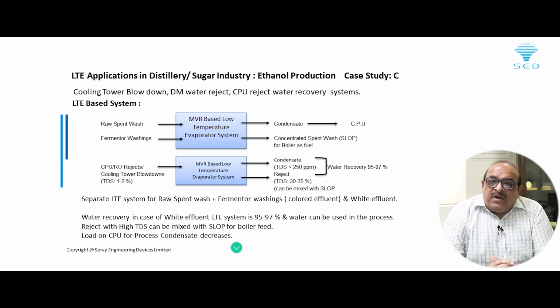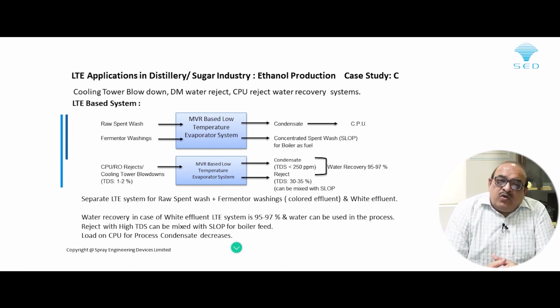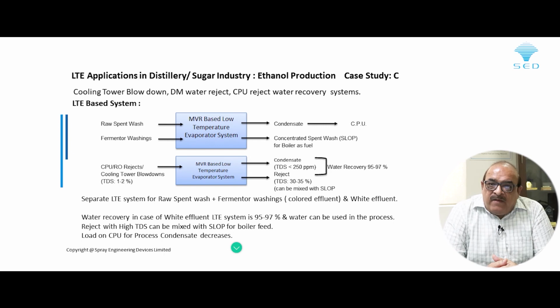And the water which will be coming out will have less than 250 ppm of TDS, which can be directly used in your process. In some cases, you may require some aeration or some pH adjustment. But the thing is, you can use this water very easily without disturbing the whole plant, and you will get good water recovery out of it. Then why not do it? In this way, the load on the CPU for process condensate also decreases, so your operating expenses will come down. Your capex requirement will also come down. So this is another example where we can utilize LTE.